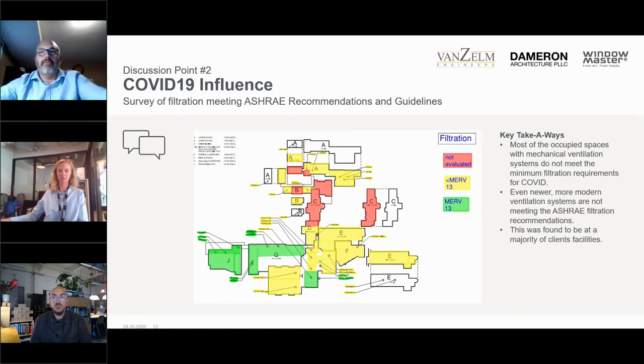What we've been recommending, and what ASHRAE recommended, is to reinstall and put in new MERV rating filters. The good news is MERV 13 is available in multiple sizes, so you can put it in a 1-inch, 2-inch, or 4-inch deep filter and it'll work. Obviously, the deeper the filter, the quicker it could potentially load up. It has a higher efficiency, so it's a little bit taxing on maintenance, but most of the facilities we're dealing with are understanding of that. A lot of it is just getting the filtration level up to what's recommended, and it'll be a better condition for a lot of existing systems.